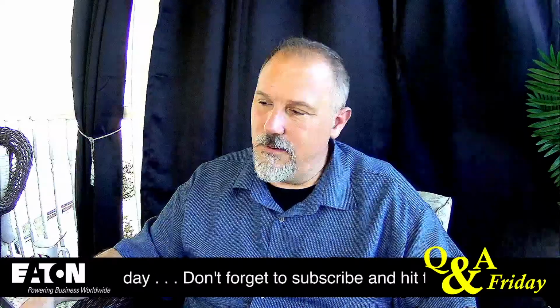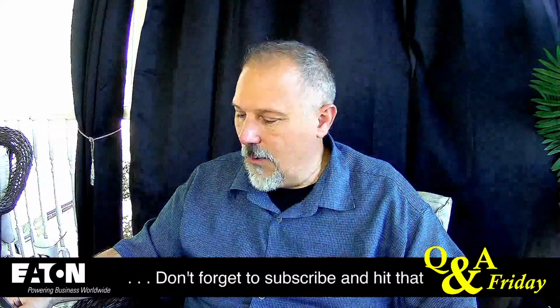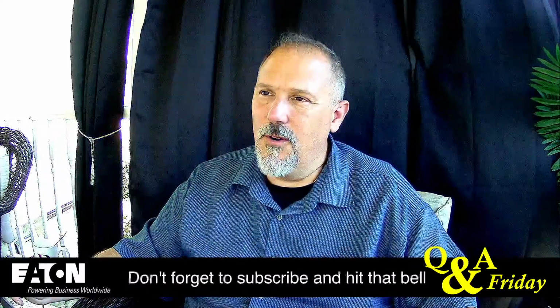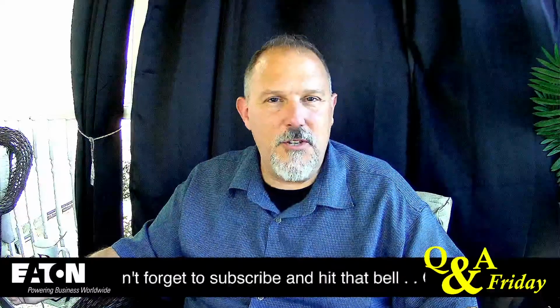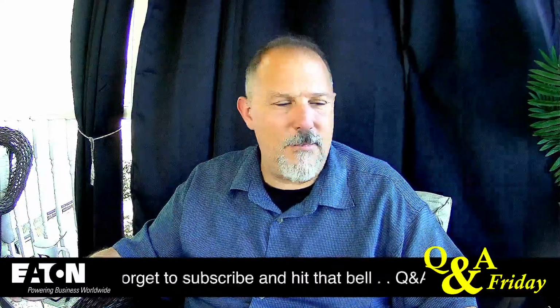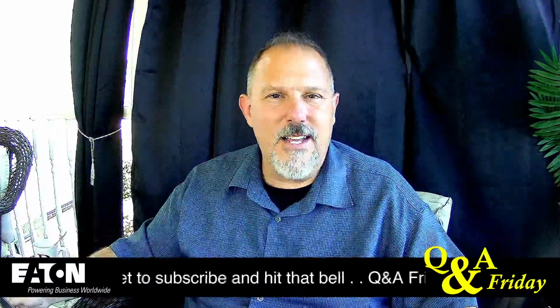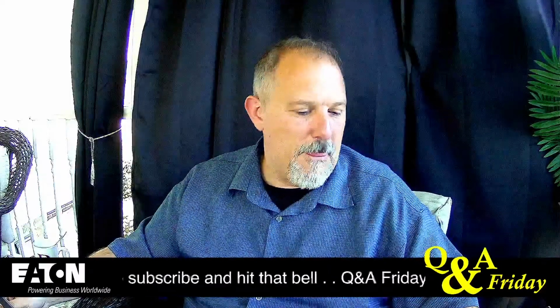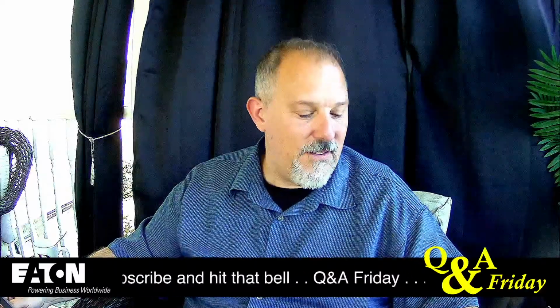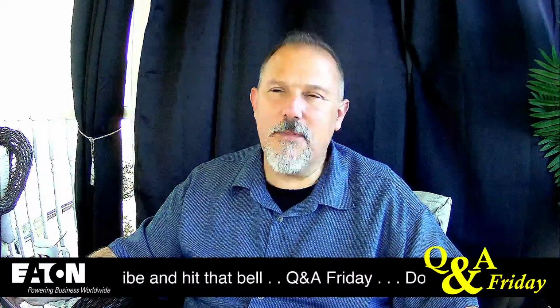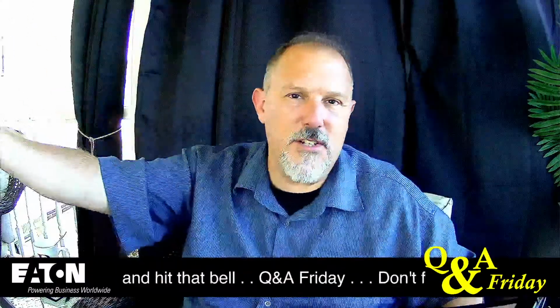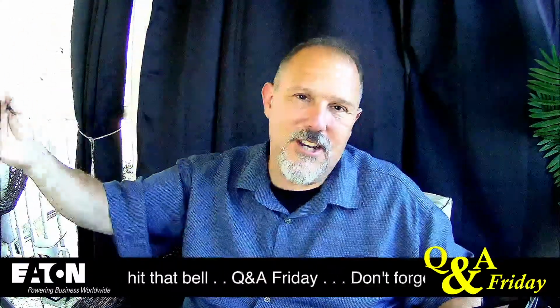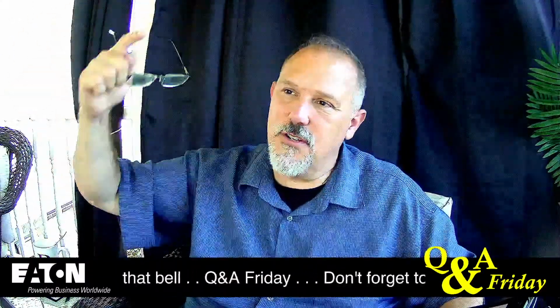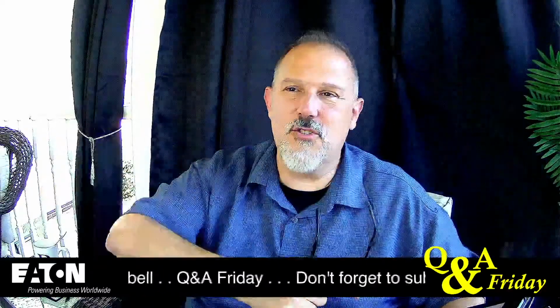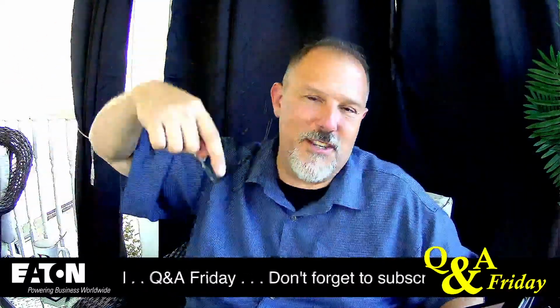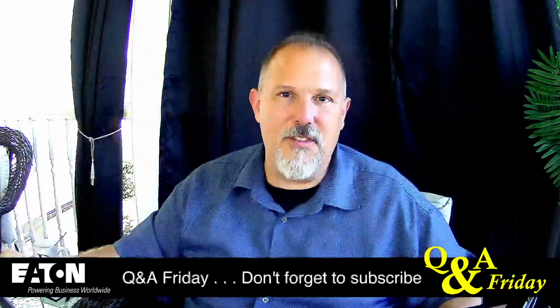That's a good question. Why do we do that? Or, I told you that you need to pull a neutral, but why? If I can't tie it back to a code requirement, then it's personal preference. So I could not find that information. I'm like, well, it's a service. So we walk down through the logic. It's connecting to the service. Those are service conductors. You have to follow 230. 230 is going to point you over to 250. 250 tells you this, and you can get there the long way.